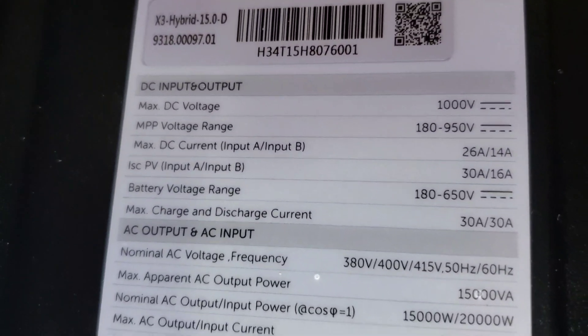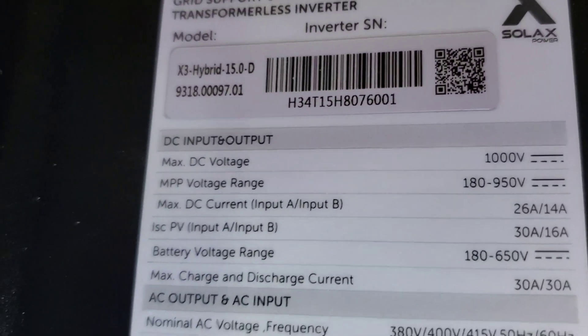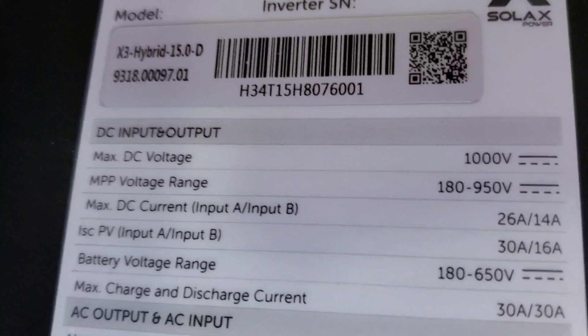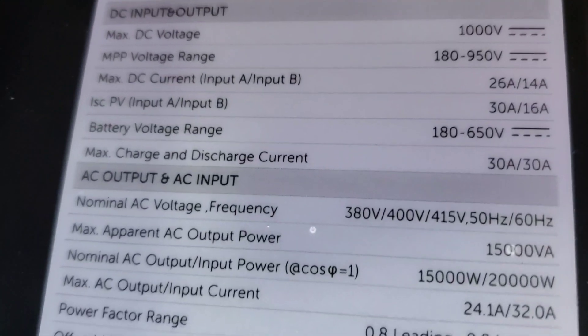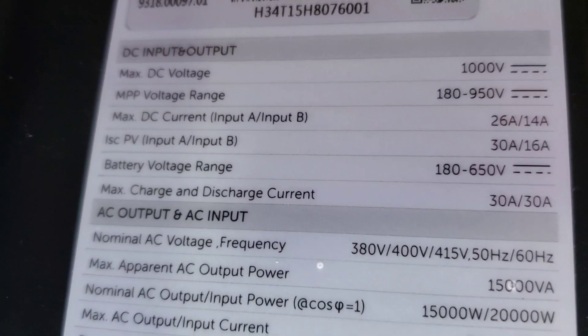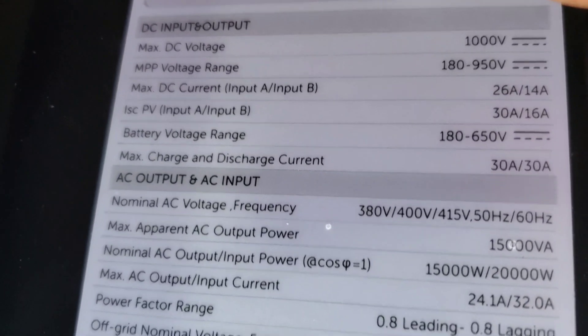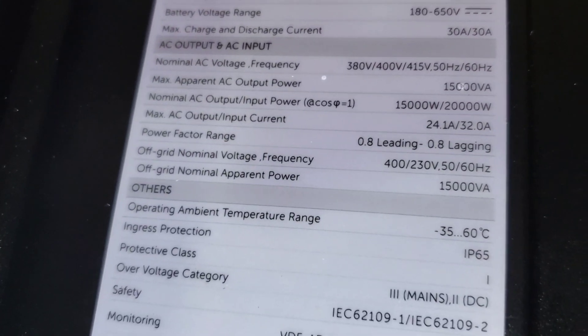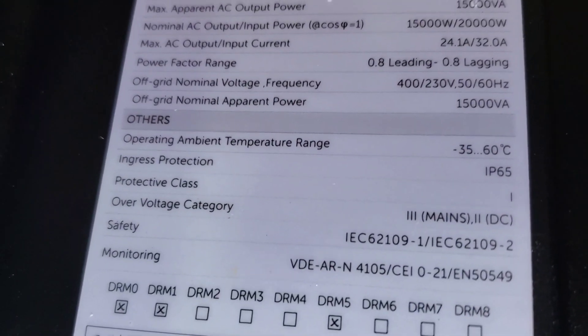DC voltage: 1000 volts — wow, this is sweet. MPPT voltage range: 180 to 950 volts. 26 amps, 14 amps — that's nice. PV input A and B: 30 amps, 16 amps. Battery voltage range: 180 to 650 volts — holy smolies, that's nice to see. On this one I need to put three batteries for custom modular lead-acid batteries to get the number I need. It's IP65 rated as I said.